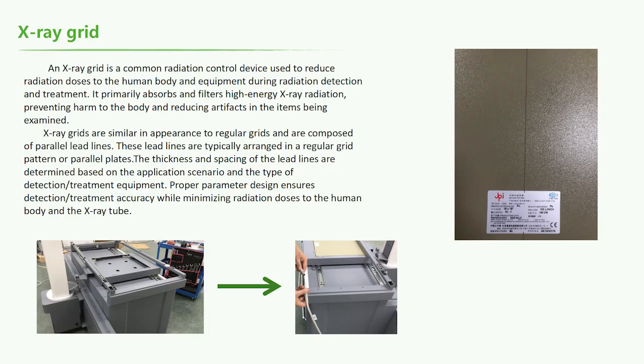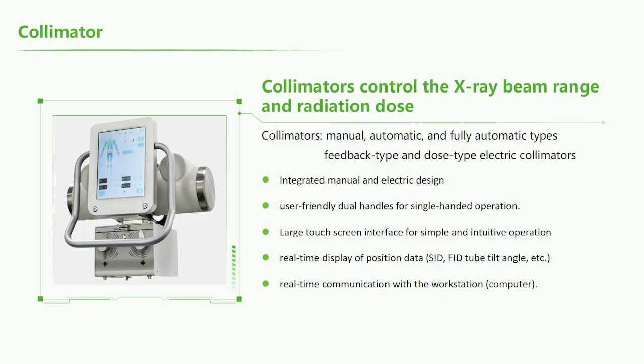The pictures in this slide show you where the X-ray grid is placed in the X-ray machine. The cube at the bottom of this picture is called the collimator. It controls the X-ray beam range and radiation dose. There are many types of collimators, for example, manual, automatic, and fully automatic. Some electric collimators can be controlled by feedback of the X-ray dose.